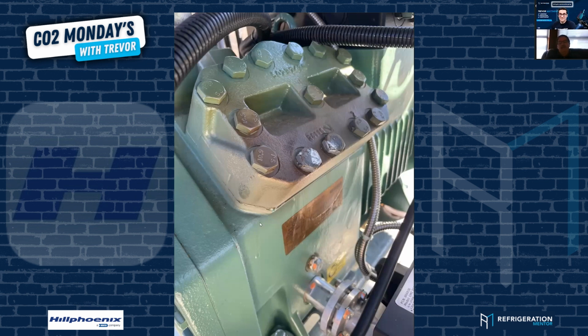So what happened is the contractor did all this. Besides all the other verifications he didn't do, he didn't check his dip switches, and his high gas dump was dumping into the rack all July and August, when we were running anywhere from 1200 to 1300 psi because this was an air-cooled rack. It was bad enough that it actually changed the color of our taps that were going to the discharge line, and on the Güntner condenser, the yellow tags that are always yellow were baked yellow just like that one, or brown. So yeah, this system got hot.